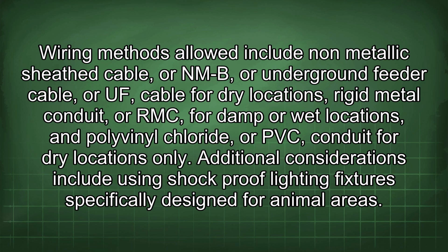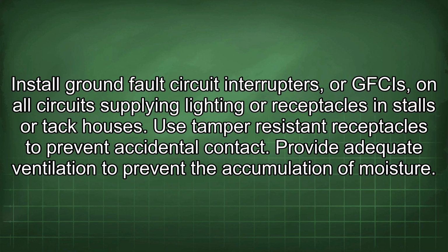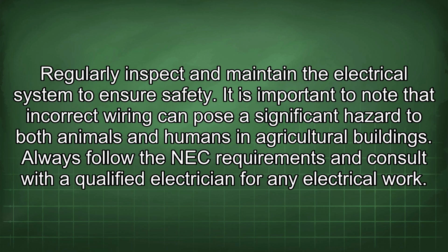Additional considerations include using shockproof lighting fixtures specifically designed for animal areas. Install ground fault circuit interrupters, or GFCIs, on all circuits supplying lighting or receptacles in stalls or tack houses. Use tamper-resistant receptacles to prevent accidental contact. Provide adequate ventilation to prevent the accumulation of moisture. Regularly inspect and maintain the electrical system to ensure safety.